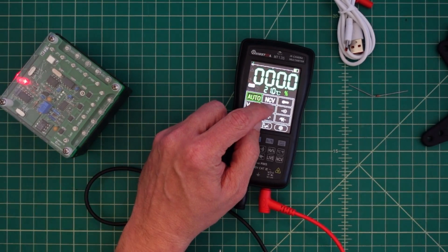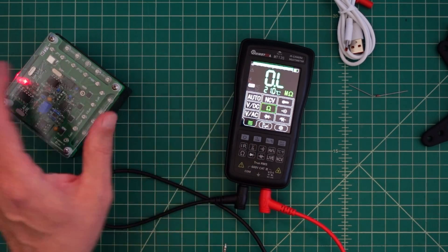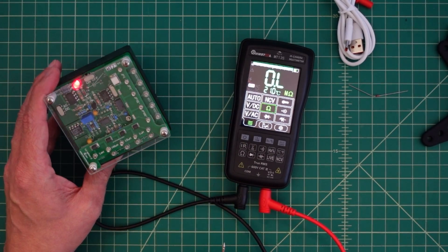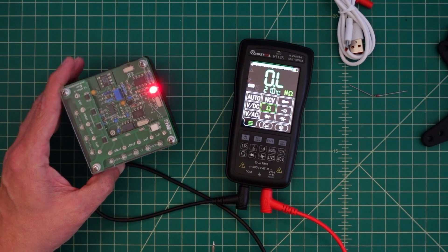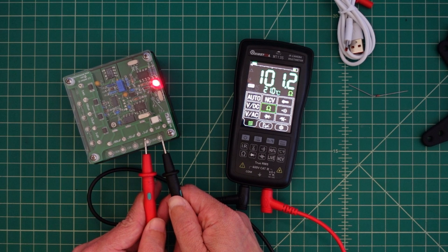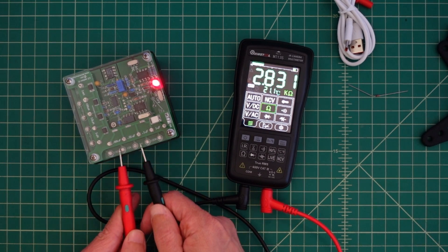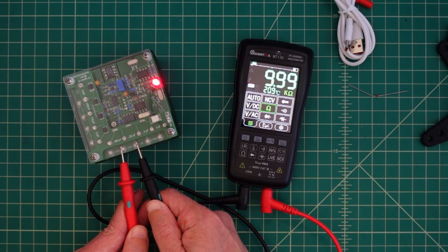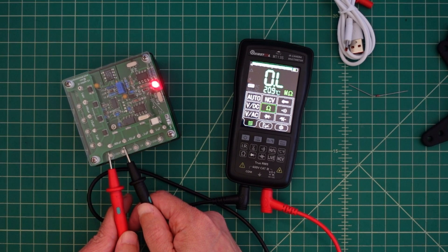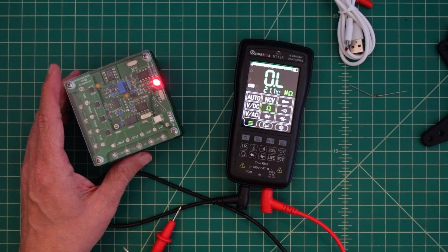What I want to do now is click the touchscreen and we've switched over to ohms. I have some resistance standards here. This first one is 100 ohms and we are at 101.1. This is 1000 ohms and it's reading 1 kilo-ohm. This is 10K and it's 9.99. And this is 100 and it's 99.9. All of that seems okay to me.